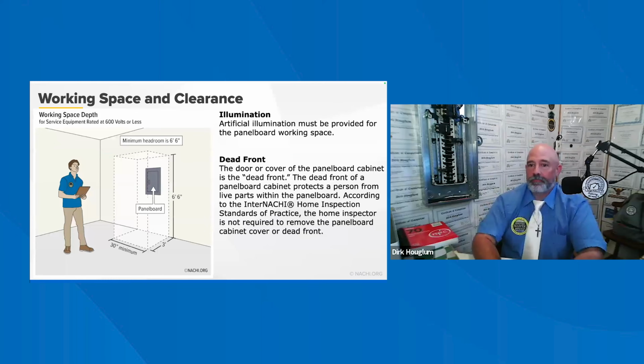So adequate space should be provided around the electrical panel board for safe access to the components. This is one of these call-outs that I call out quite a bit. The working space in front of a panel board must be at least 36 inches. That's 914 millimeters, yes. The working space must be at least 30 inches, 762 millimeters, wide in front of the electrical panel board and at least 6.5 feet in height, and this is 1,981 millimeters. Panel boards must not be located in bathrooms, toilet rooms, clothes closets, or over the steps of a stairway. The overcurrent devices must be readily accessible.